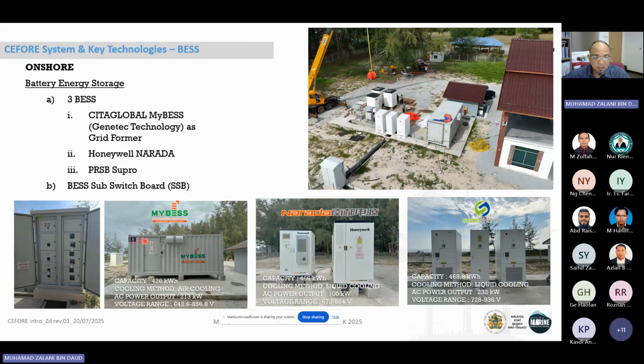This one serves as our grid forming battery energy storage, providing frequency and voltage reference to the rest of the inverter-based system. This is the key technology to replace the diesel generator, because this is an off-grid system. We need to control the voltage and frequency at 400 volts, and the frequency should be within 50 hertz for the inverter to synchronize with the grid.